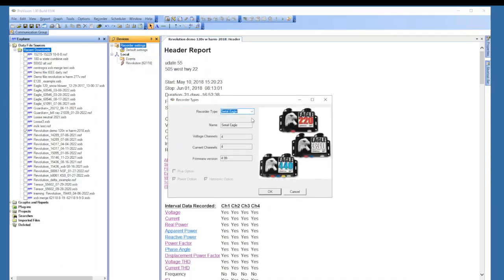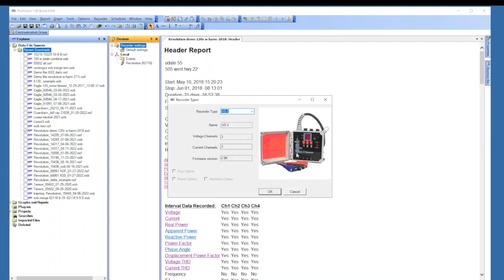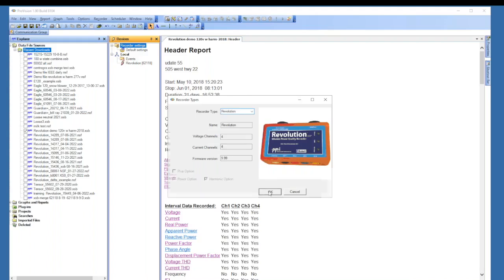Now, the other thing you can do is create a template. So you don't even need the recorder. If you have a recorder on site and you know you're going to go out there and change it, you can set up a template. You do that by right-clicking on recorder settings and then choosing create template settings. And then you choose which recorder you're going to use. As you click on these, you'll get a picture of the recorder. So if you know that's not your recorder, then you have the wrong one selected. And we'll click on the Revolution.